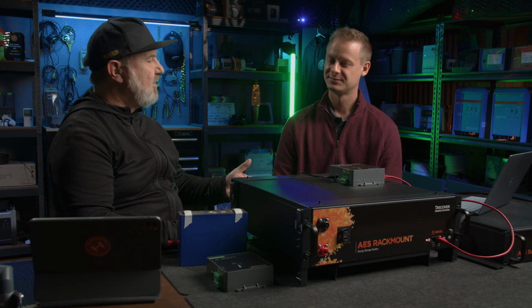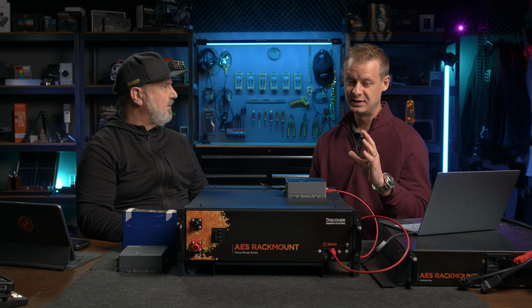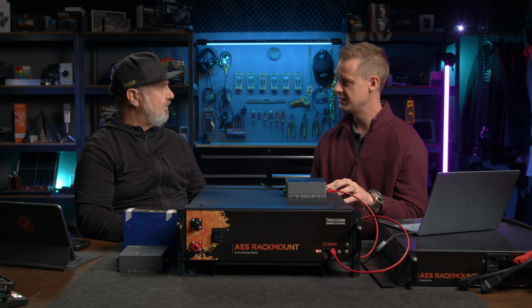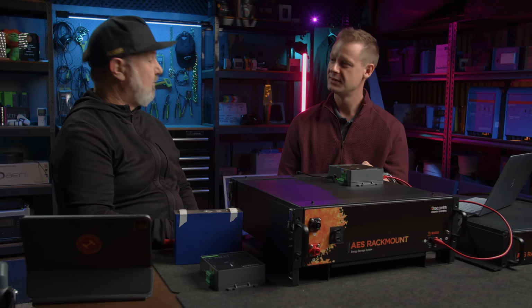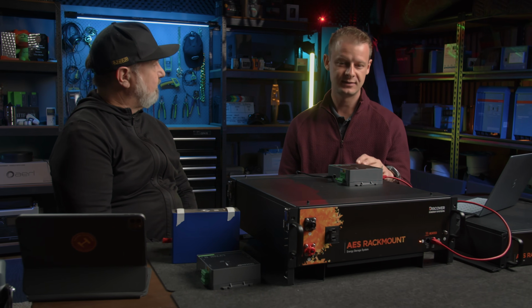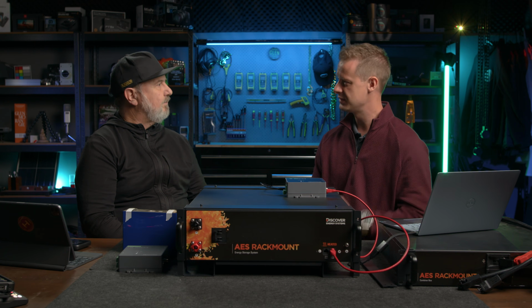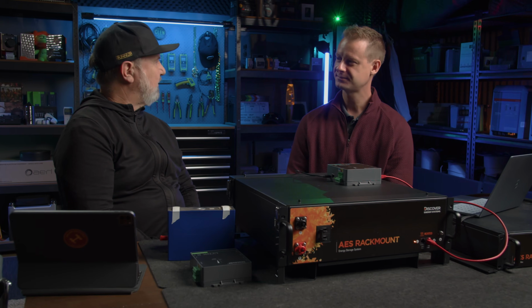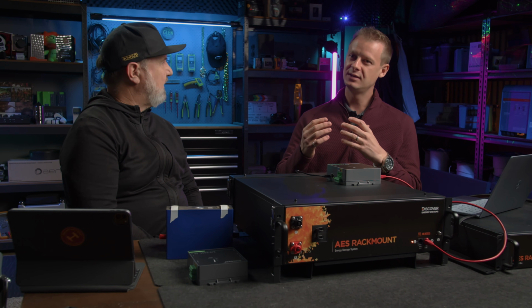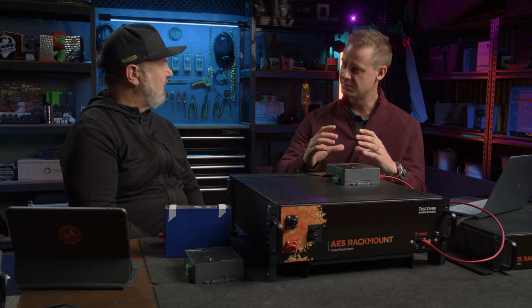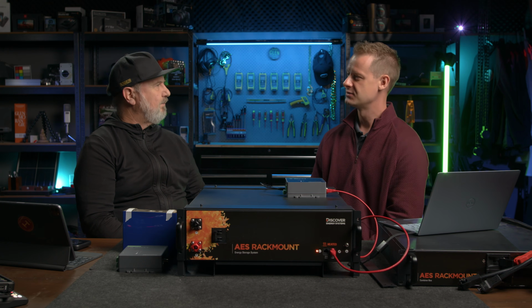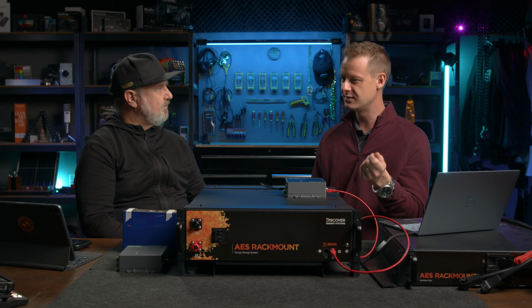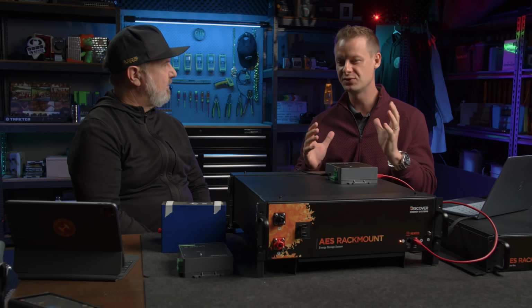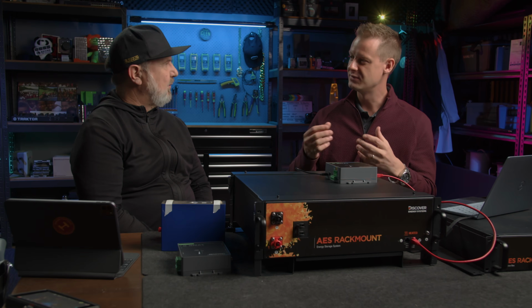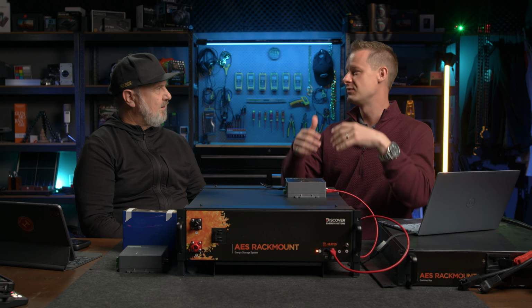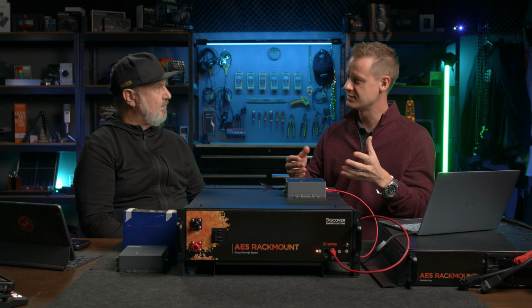You mentioned UL — which UL are these certified to? These are certified to UL 1973, IEC 62619 as well, and UL 9540A and UL 9540. The 9540A is a collection of cell level, module level, system level tests. So you get a cell, make sure it has 9540A, go through the same types of tests and reviews at the module level, and then if we've got cabinets or systems, we'll replicate those tests yet again.